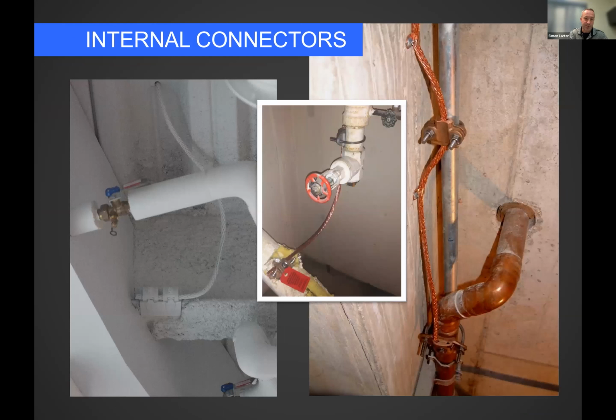And then, of course, we've got the bonding connections on the interior to a steel beam, to the water piping and all that, an electrical conduit there. We do want to make those connections on the inside too. We are required, and you know this, to have interconnections between our grounding system and everybody else's grounding system: the electrical, water pipe, gas piping, telecommunications. We do have to connect up to all of that. I'll go over that in a bit more detail when I get down to the codes and everything.